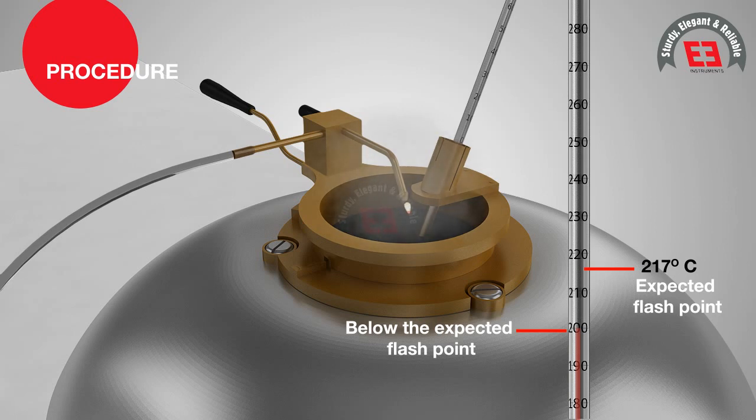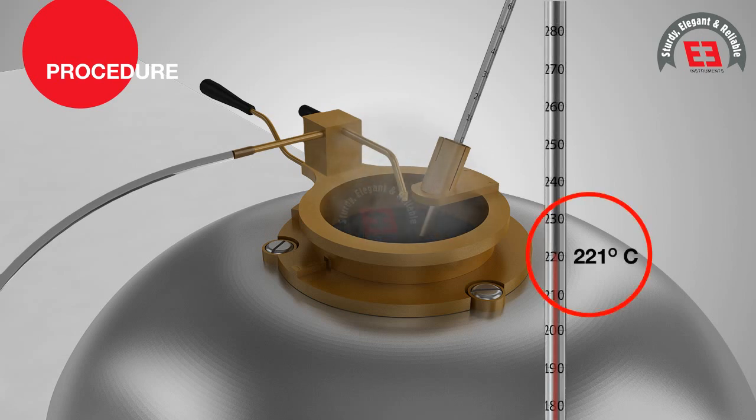the test flame is applied on the surface of the sample with the help of burning matchstick at every rise of 1 to 3 degrees Celsius. When the flash occurs for the first time, the temperature at that instance is recorded as the flash point under open cup test.